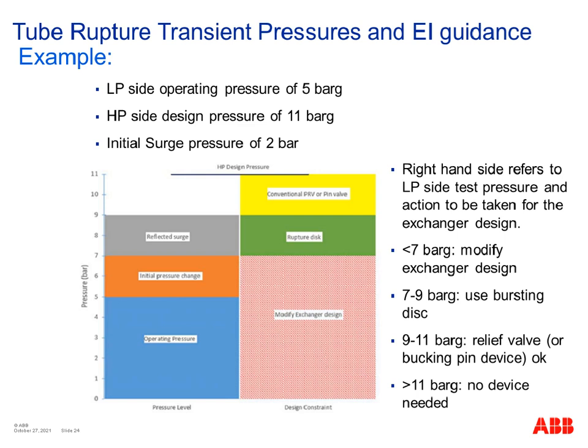If instead the LP side test pressure is greater than 9 but less than 11, then you would be allowed to use a relief valve or a buckling pin device if you preferred. And if the LP side test pressure was greater than 11 bar gauge, then you wouldn't have a concern and you wouldn't need a relief device at all, because you'd be saying that even if this event occurs, I'm not going to overpressure my LP side of the exchanger. So I don't need a relief device for that scenario. You may need the relief device for other scenarios that we've already talked about in previous sections.